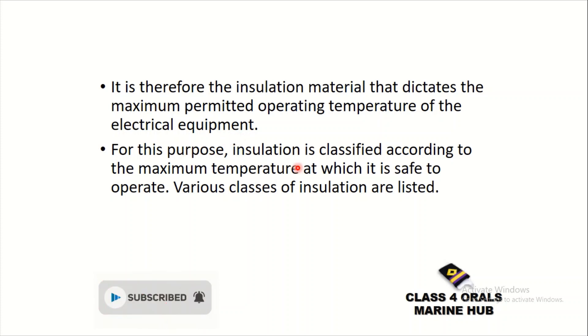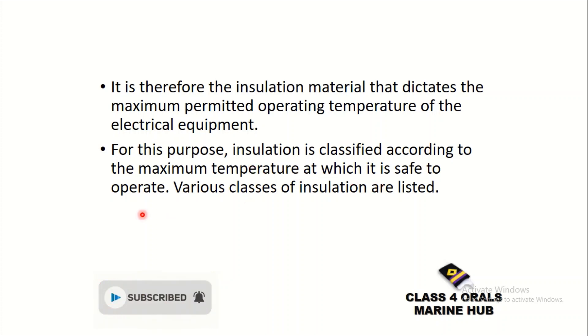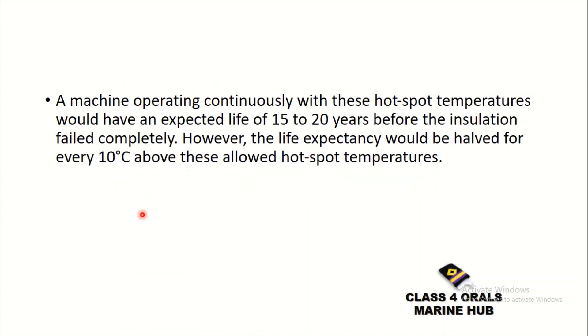For this purpose, the insulation is classified according to the maximum temperature at which it is safe to operate. The various classes of insulation are listed. A machine operating continuously at these hotspot temperatures would have a life expectancy of 15 to 20 years before the insulation failed completely. However, the life expectancy would be halved for every 10 degrees centigrade above these allowed hotspot temperatures.